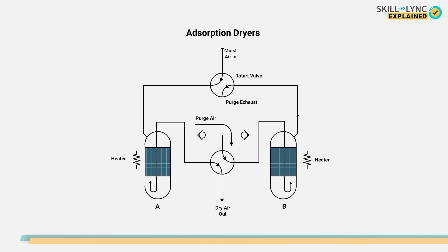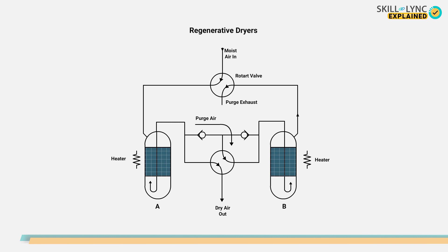By using two columns of such filters, continuous filtration can be achieved, where one column filters the moisture from the incoming air while the other column is heated to release the adsorbed moisture. Due to this property of reusability, adsorption dryers are also called regenerative dryers. Thus, the primary air treatment is completed.